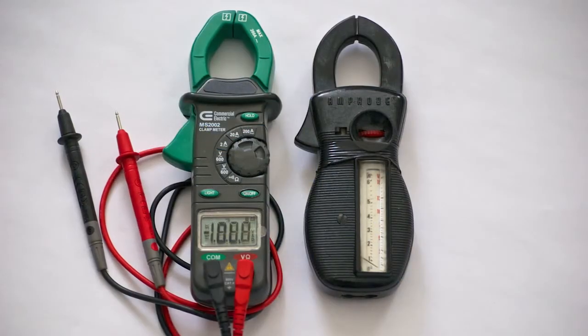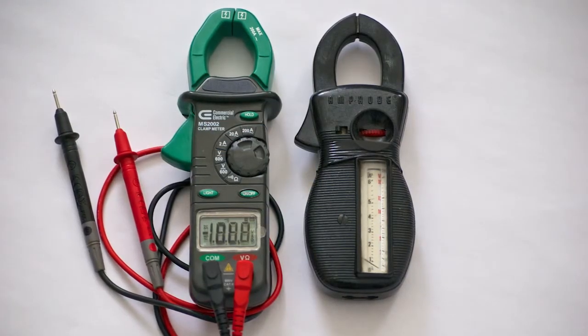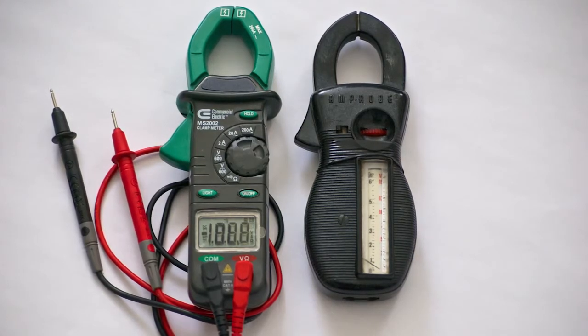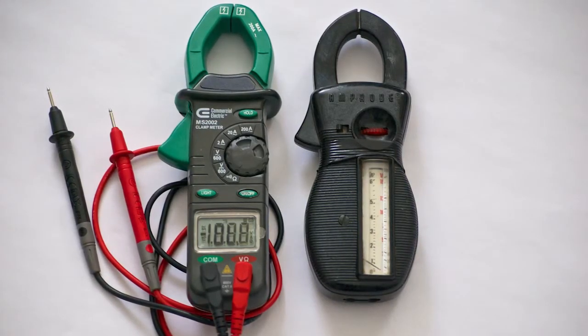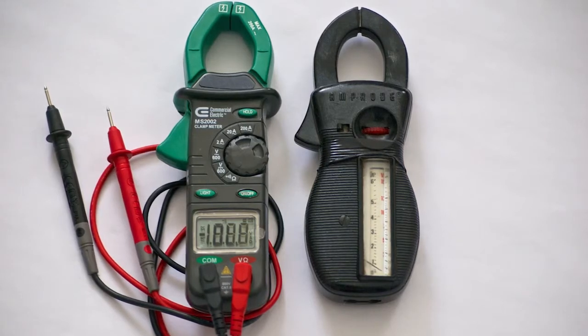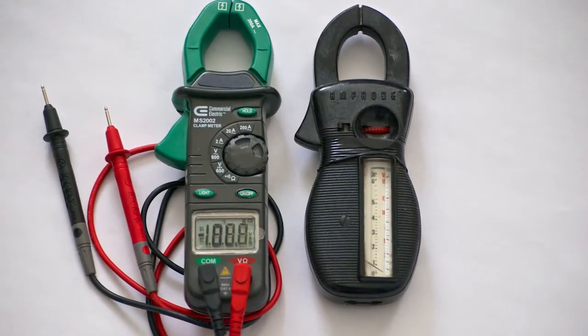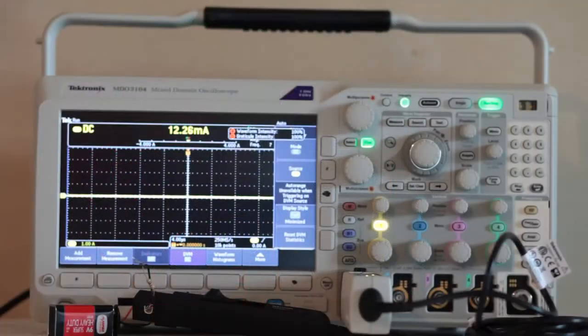For electricians, both of these problems have been solved by the development of the clamp-on ammeter, trade name Amprobe. It has jaws that can be opened and clamped around any insulated live conductor. What is measured is not the actual current, but instead the magnetic field surrounding the wire, which varies with the amount of current. A stable reading is produced regardless of whether the conductor is centered in the jaws and whether the conductor passes through the jaws at an angle.